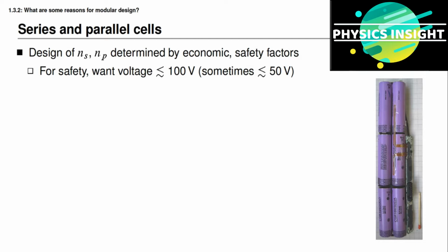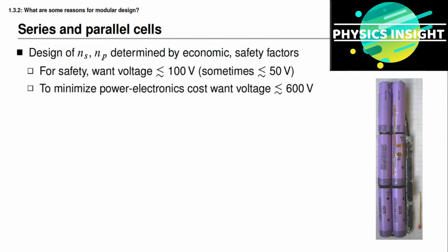Different professional and standards associations come up with slightly different answers as to what is a safe DC voltage. For example, the National Fire Protection Association (NFPA) historically had a maximum voltage limit of 50 volts DC before considering a battery a safety hazard, and more recently raised that value to 100 volts DC. Automotive manufacturers tend to be very conservative, preferring voltages of less than 50 volts in any part of the battery pack that might be exposed.